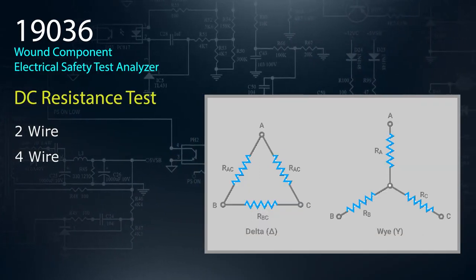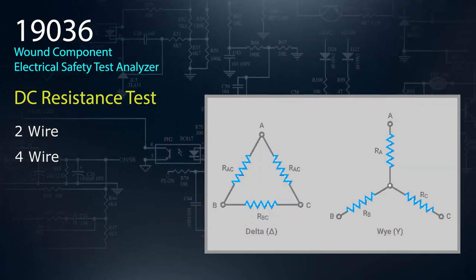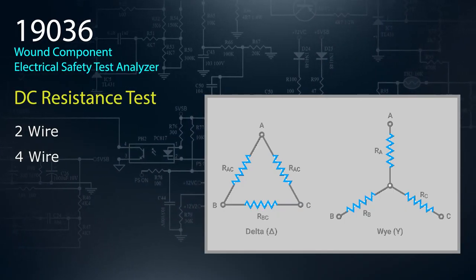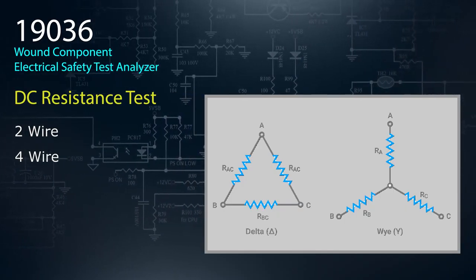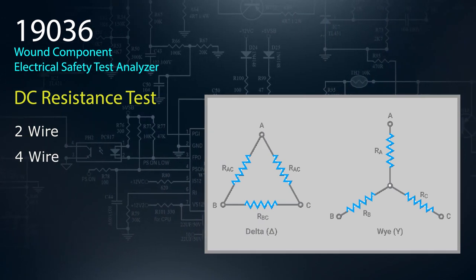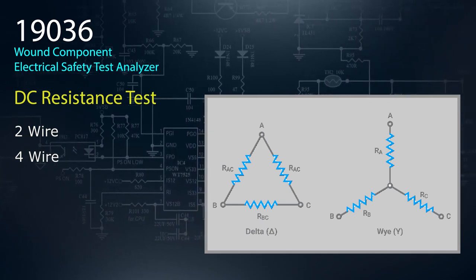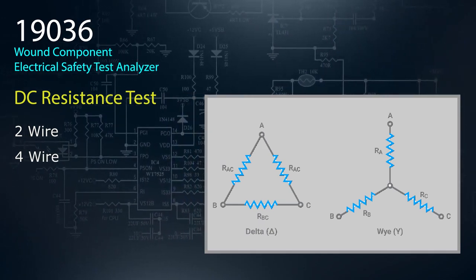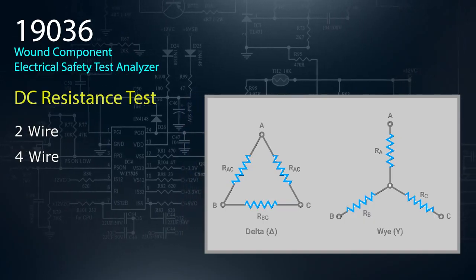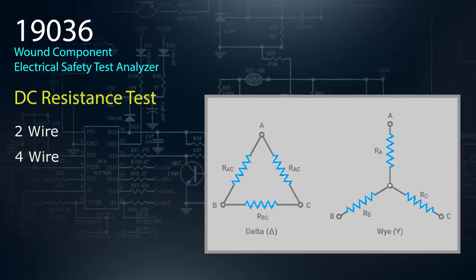Its design allows for high-accuracy 4-wire DCR measurements covering a wide range from very low resistance to very high resistance and includes both drive and sense terminals. With built-in calculation functions, DCR measurement can be achieved on either delta-type or Y-type motor windings.